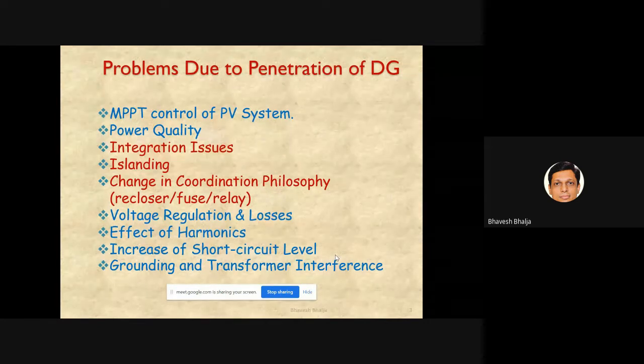So then you have coordination issues between the relay, between the fuse, between the recloser. Recloser is again a device which is used by most of the utilities in our country also. We have installed reclosers, not at distribution level but at transmission level, right? Just to improve service continuity and reliability. So I hope you are aware that they are installed in our country on 132 kV transmission lines or 220 kV lines or maybe 400 kV lines like that.